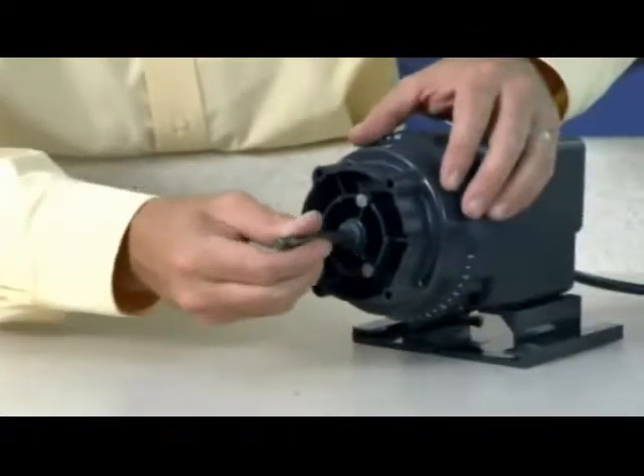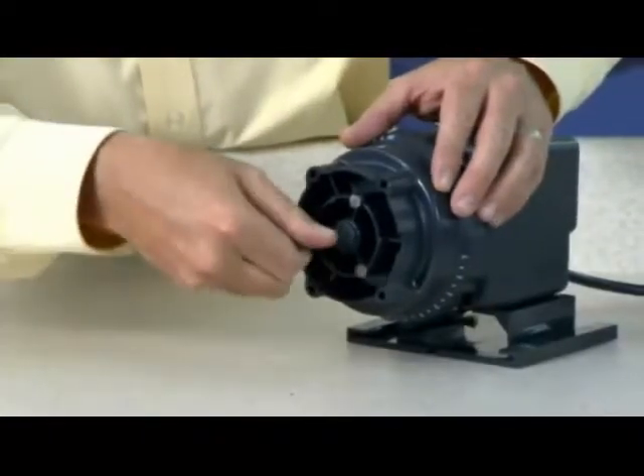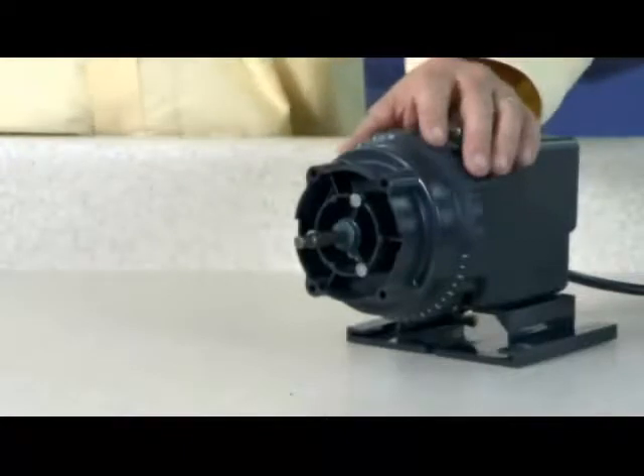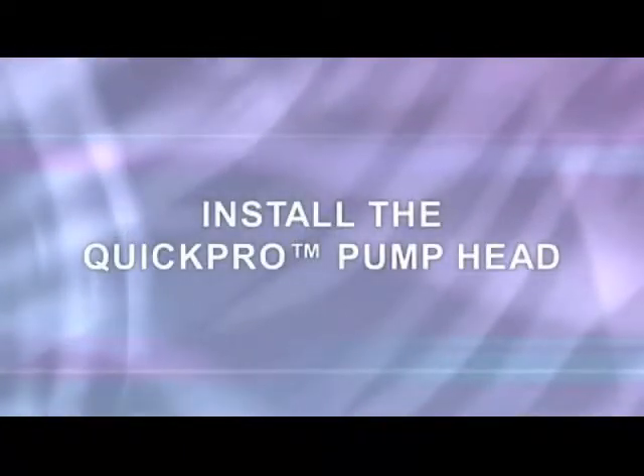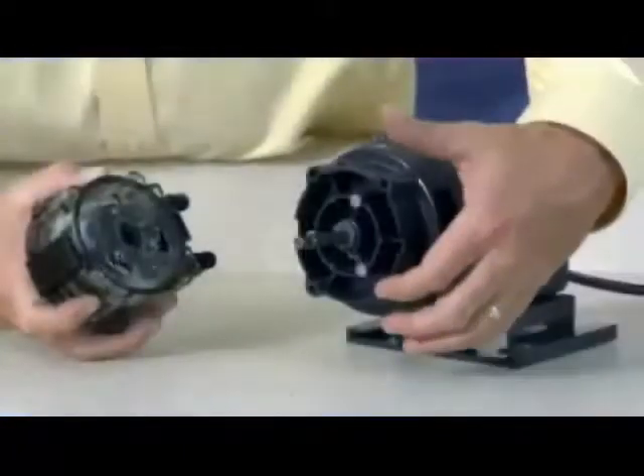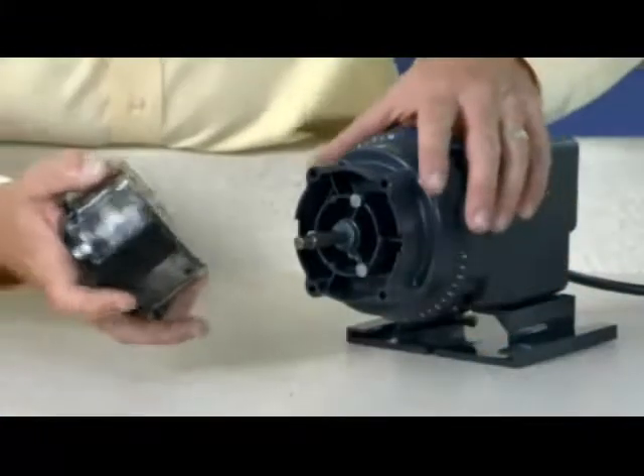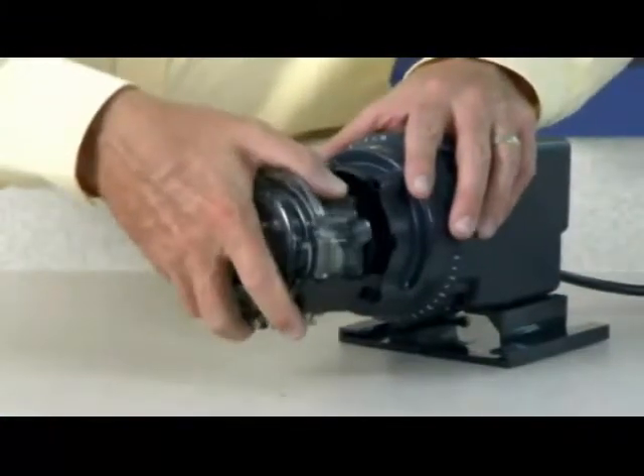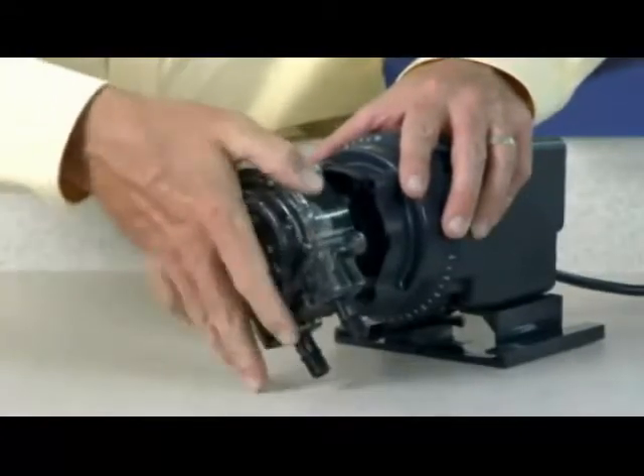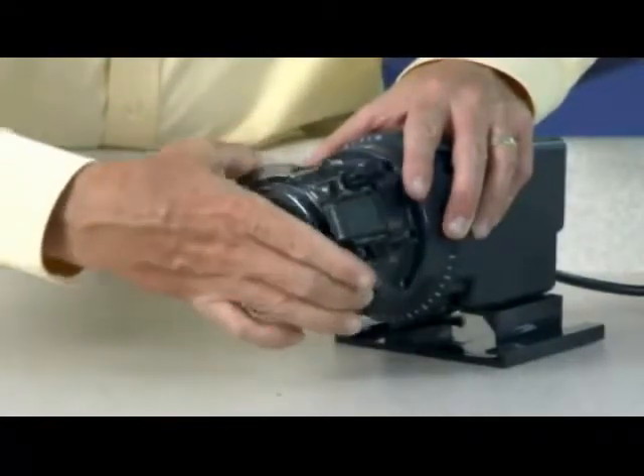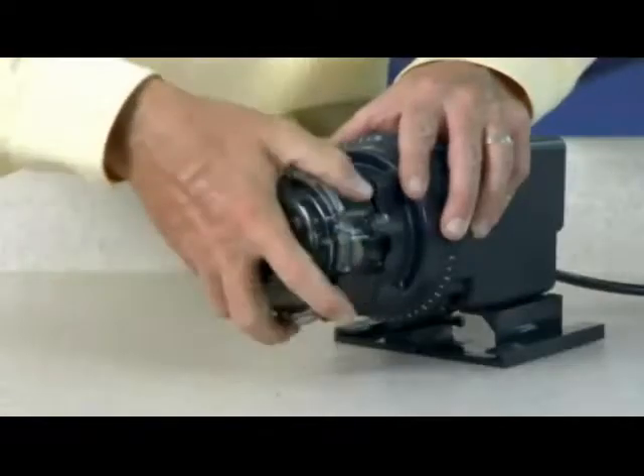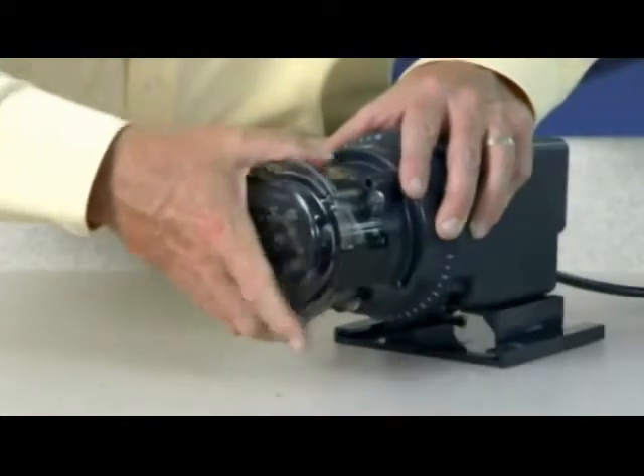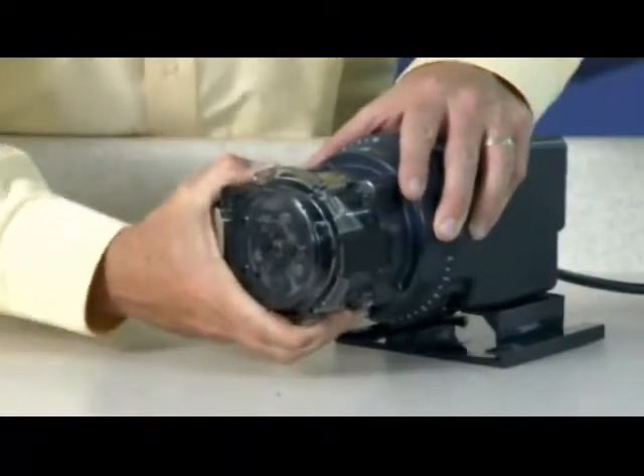Insert the shaft back into the feed rate control. Put the new pump head onto the feed rate control and turn it counterclockwise until the shaft falls into place. Push the pump head in while turning it counterclockwise. Line up the rivet holes on the pump head with the rivets on the feed rate control. Continue to push until the rivets are inside the holes. Turn the pump head counterclockwise to secure the rivets in the rivet slots, firmly attaching the pump head.